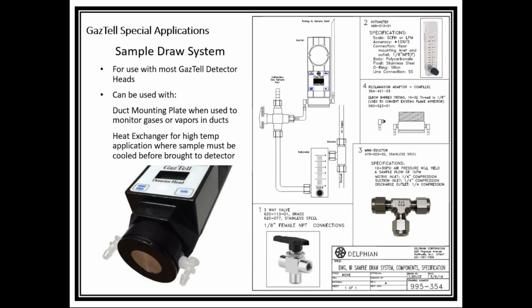These components are readily available at Delphian. You've got the part numbers. Again, this document is readily available on your rep website. And the difference between the ported adapter and the reclamation adapter is that the ported adapter has one elbow to send gas up to the sensor, and the flame arrestor is open. With a reclamation adapter, we close the entire flame arrestor opening, and now we have an inlet and an outlet. And that's the difference between the two.